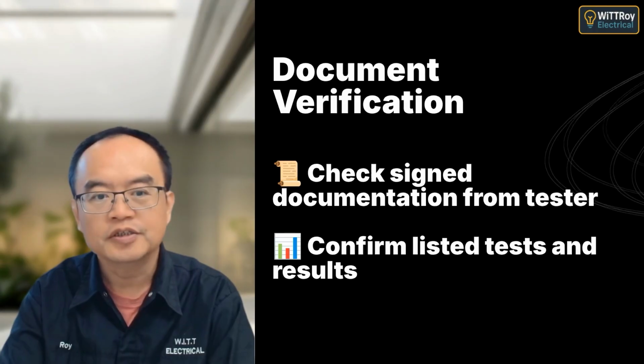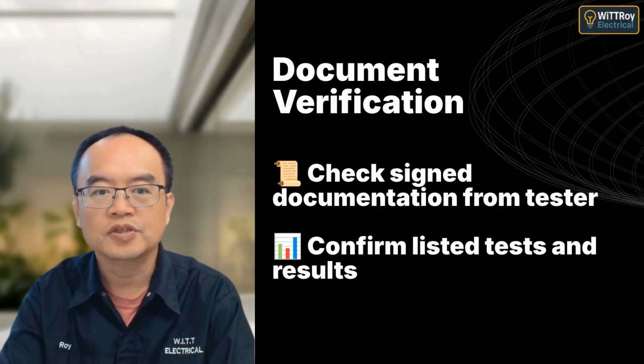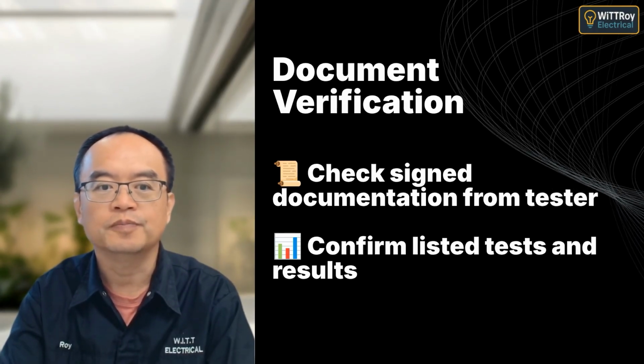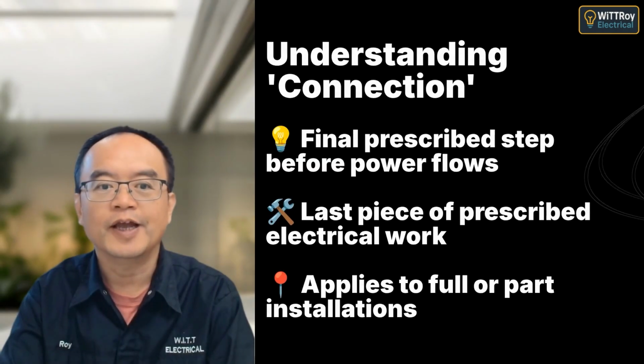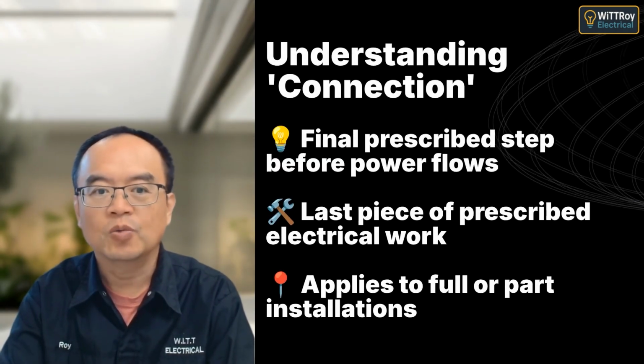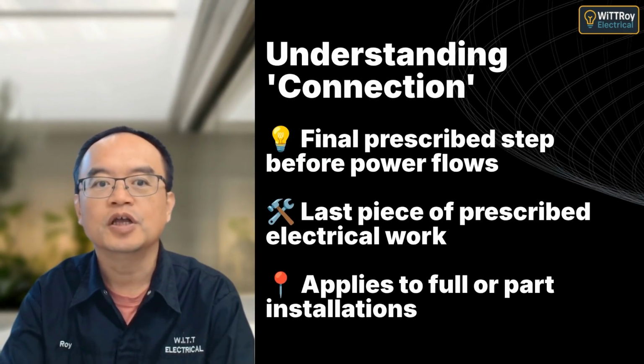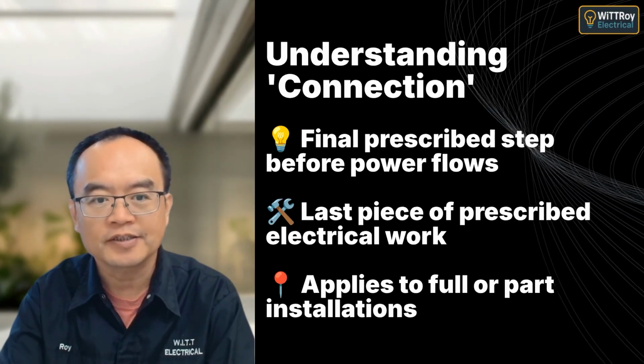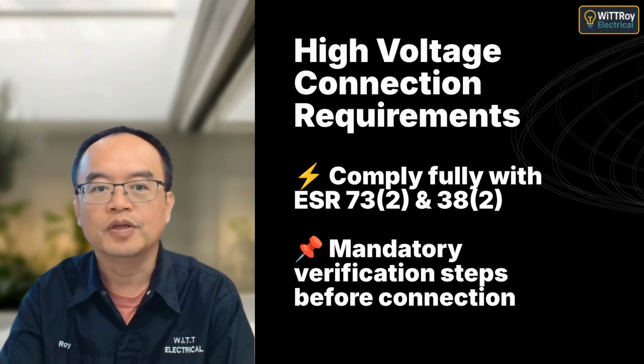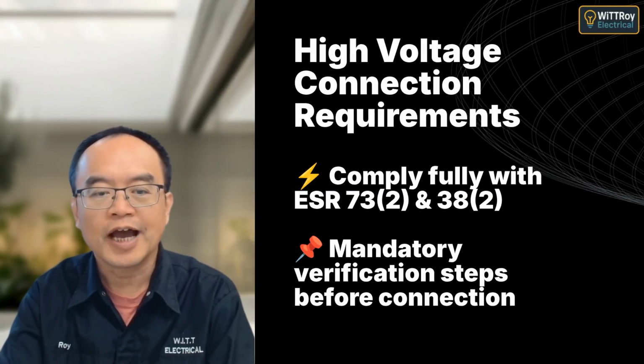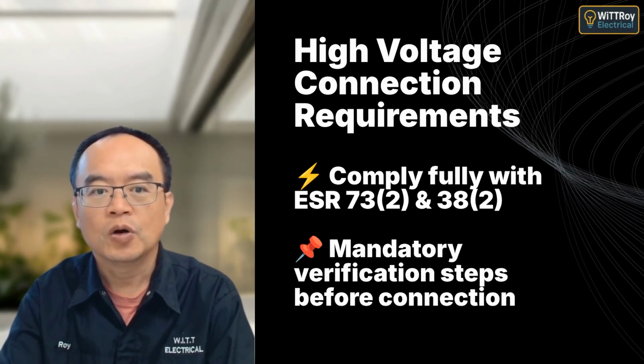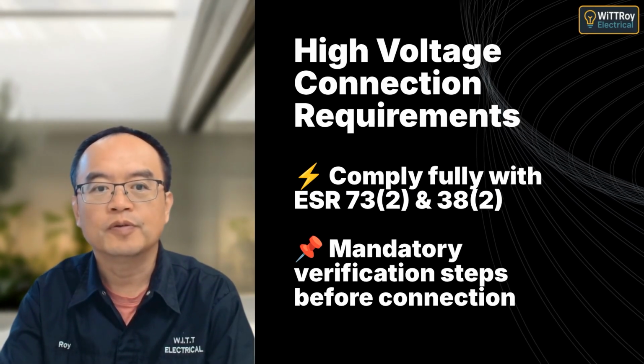If you didn't do the testing, you must check signed documents that show what was tested and the results. Connection means the final piece of prescribed work that lets electricity flow, whether it's for the full or part installation. High voltage connections require strict compliance with ESR 73.2 and ESR 38.2. All mandatory safety checks must be confirmed before proceeding.